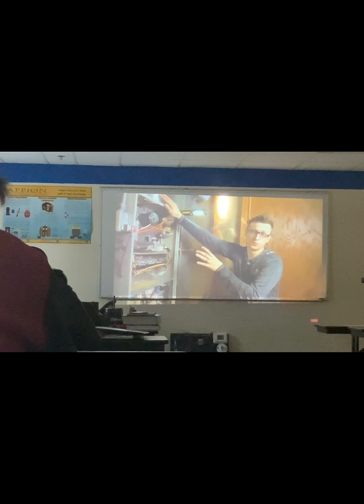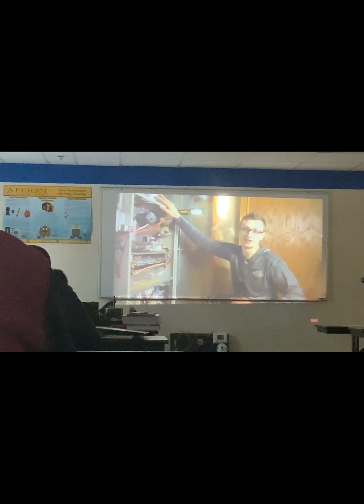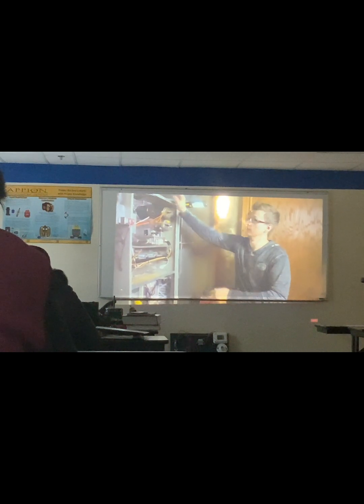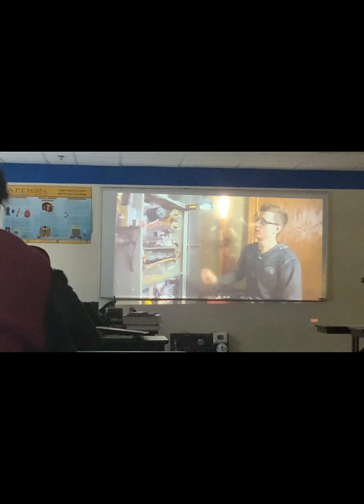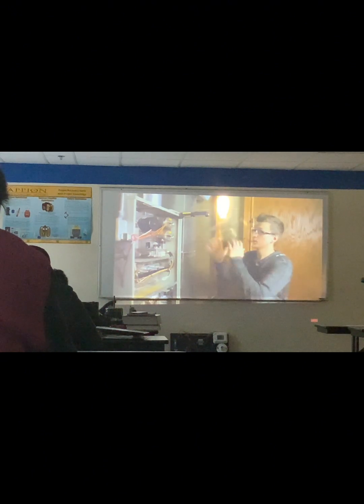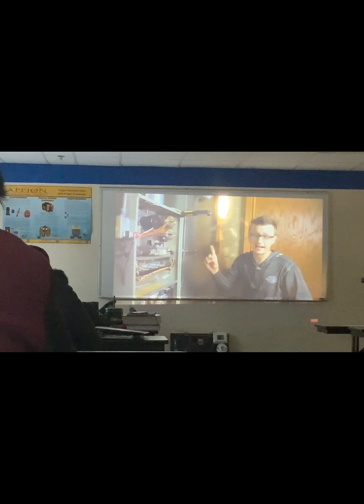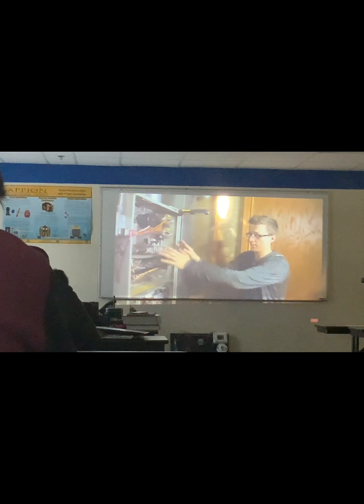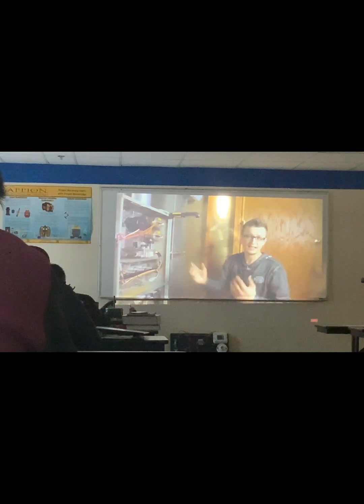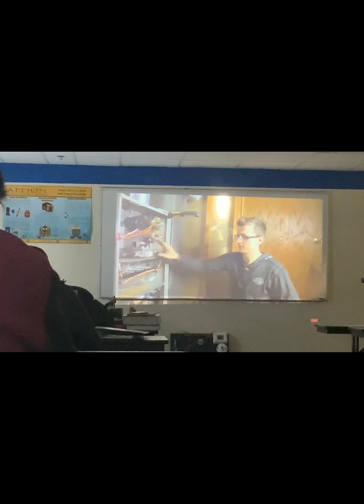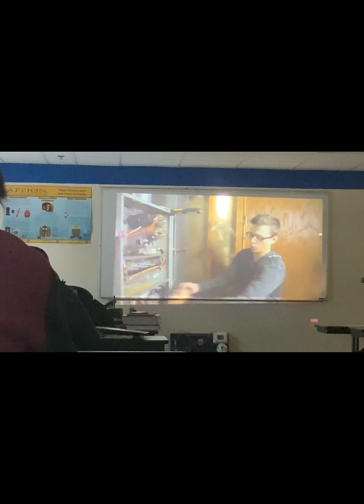Carbon monoxide parts per million will go through the roof. They'll be like 2,000, 3,000, 4,000. And then you wanna pull out your probe right away, otherwise it'll peg your meter. If the carbon monoxide going out the chimney is that high, then generally you have a problem with your heat exchanger. And if we want to visually verify if it's bad or not, sometimes you can pull the blower motor out. If you have an 80% furnace, you can pull the whole thing out, get under there and look at it from the bottom, where you see the whole heat exchanger, and try to find a crack. That's what it looks like.